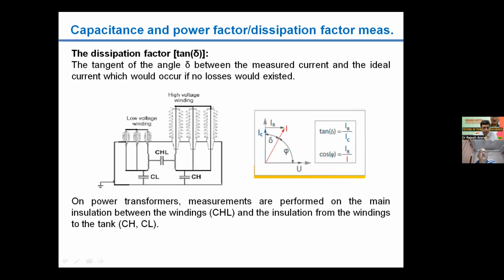Okay, sir. So the dissipation factor, as I discussed, is basically measured on the transformer, and we do 5 types of tan delta measurements. The picture indicates the capacitance between the high voltage and low voltage winding, then the capacitance between high voltage and earth, and low voltage and earth. So CHL, CH, and CL. Okay. Next.